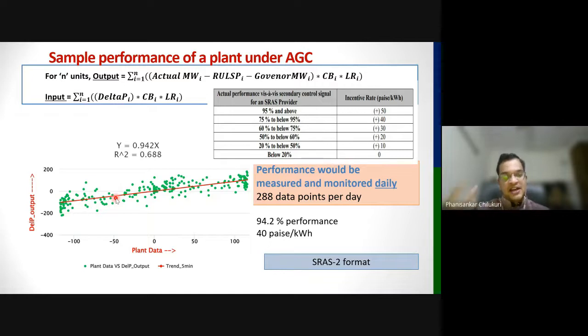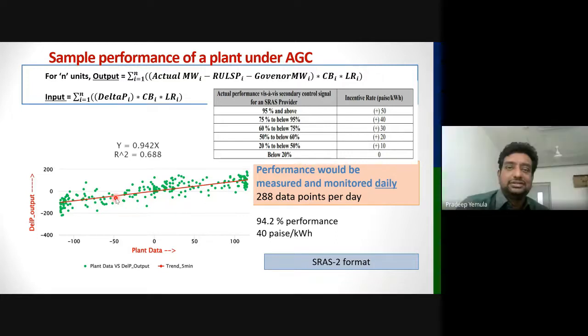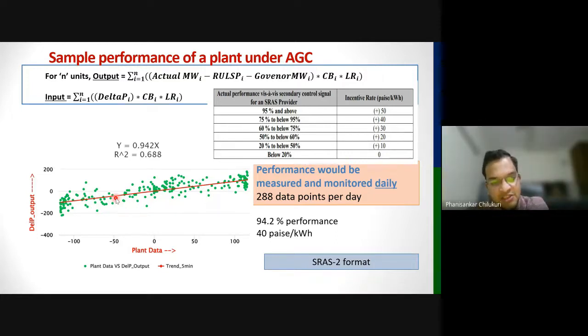In RRAS, the load set points are changed manually — manual instructions are sent from the NLDC control room. We punch them in, as shown on the display, and those are added to the schedule. In AGC, there is no scheduling; the signal directly reaches the load set point. So from Delhi to Tuticorin, the signal reaches and enters the digital control system of the power plant, and the power plant adjusts its generation accordingly, increasing or decreasing as instructed.